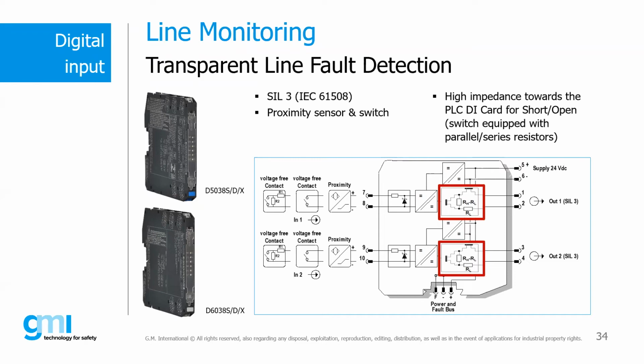But what happens in the event of a fault detected in the field? In the event of a fault in the field, whether it's a short circuit or an open circuit, the transistor in series with the output loop opens, and a high impedance is shown towards the PLC digital input card, which is read by the PLC as a bad signal or a fault. This network of resistors at the barrier output allows us to obtain a mirroring system of the fault towards the PLC.